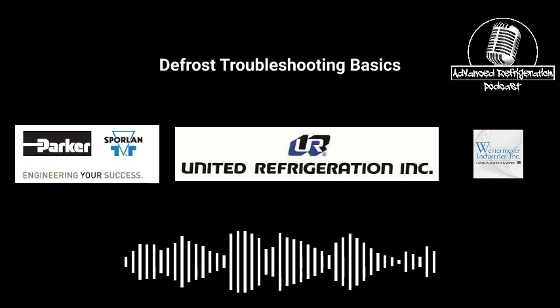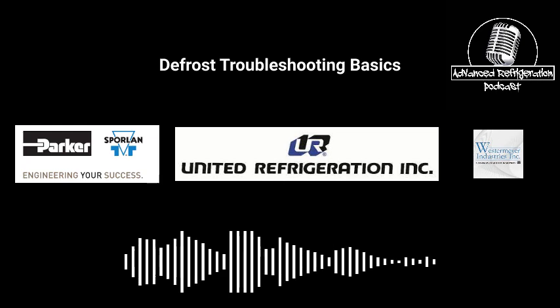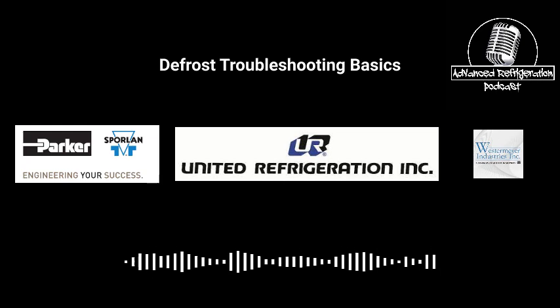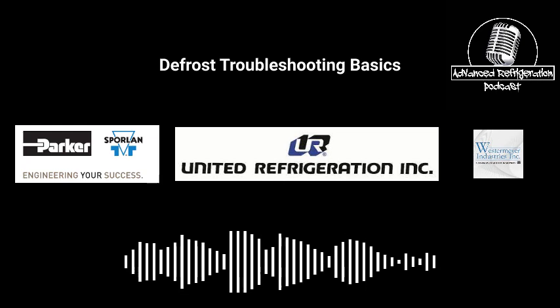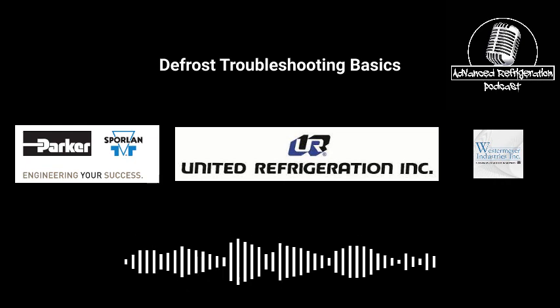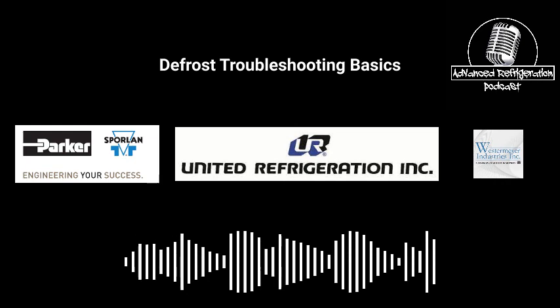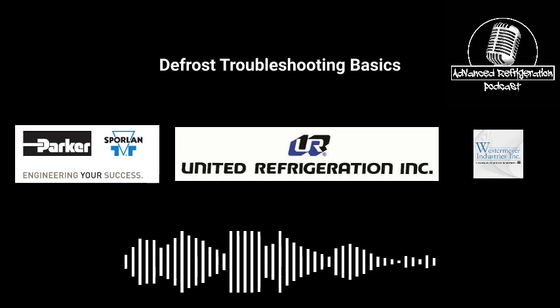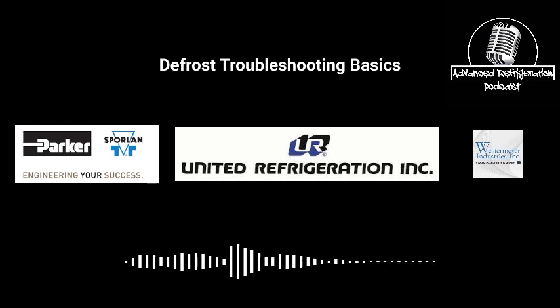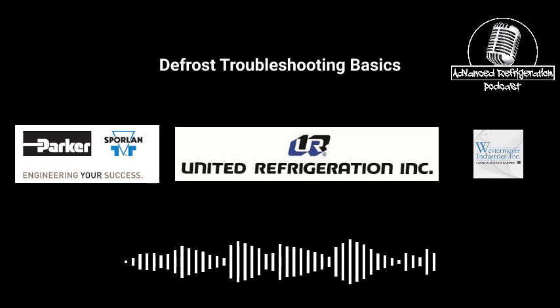A liquid differential valve is creating a differential from your receiver to your liquid header. Now, I mean, you could use both for hot gas defrost. But me personally, I would much rather see a discharge differential valve. A liquid differential valve is going to cause liquid to back up in the receiver. So at times it's going to give you erratic liquid levels, which I would like to see steady, constant liquid levels. Yeah, but why?